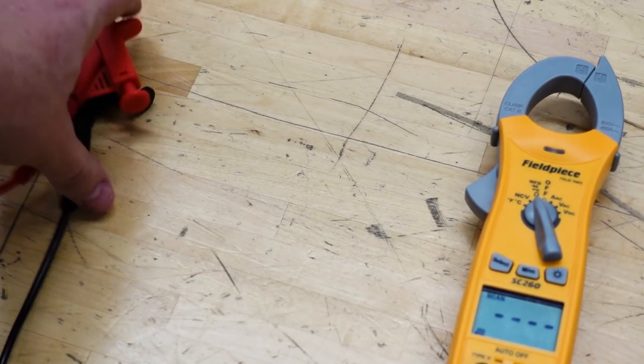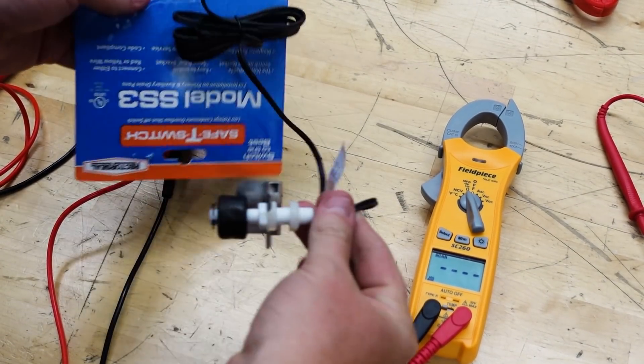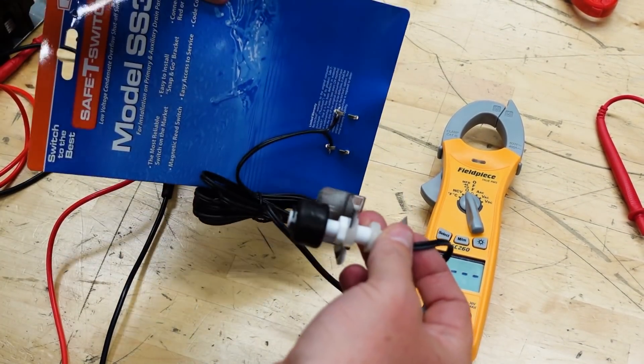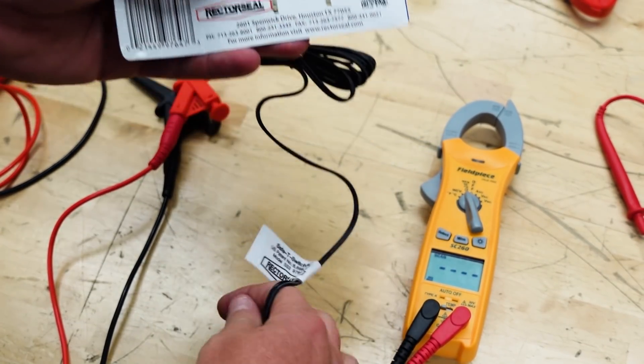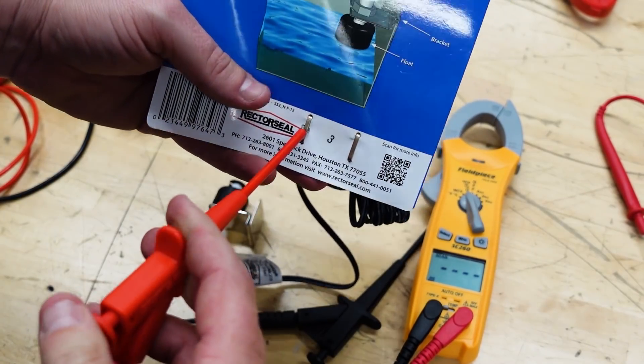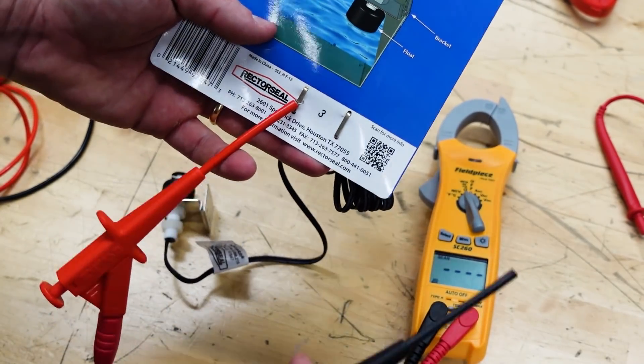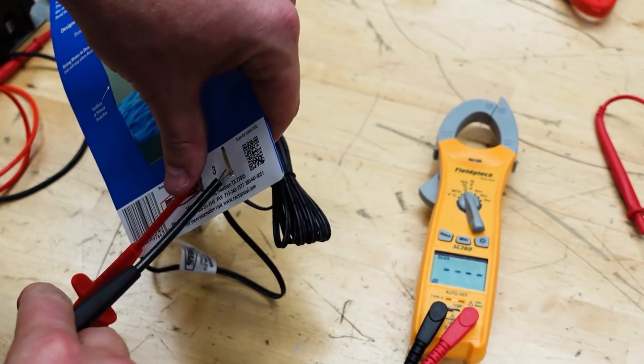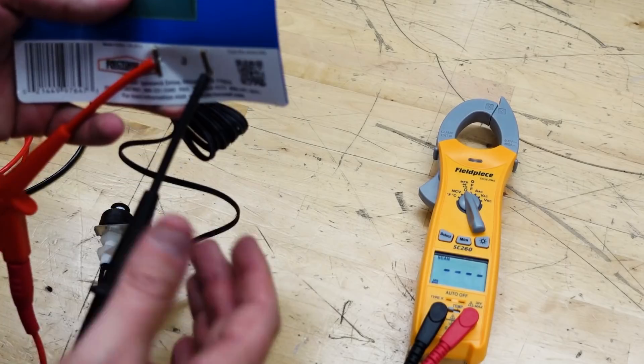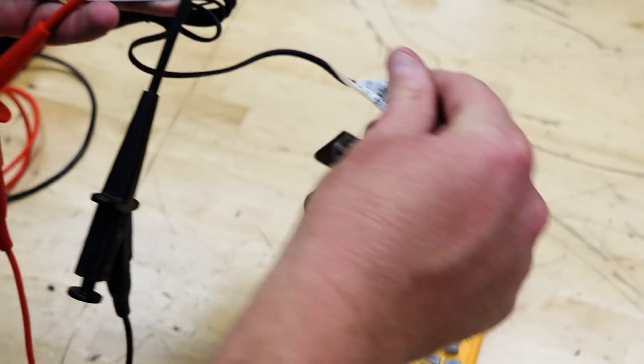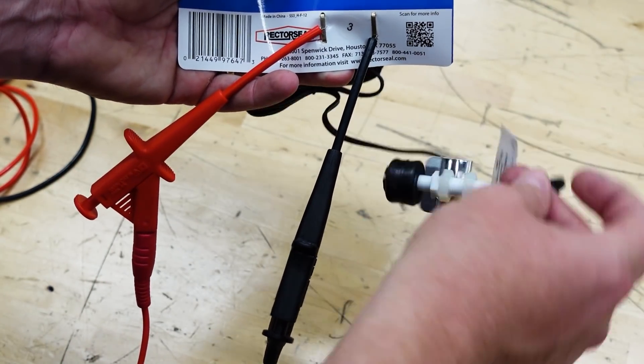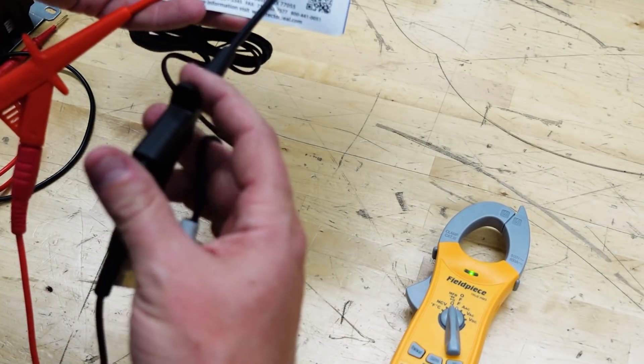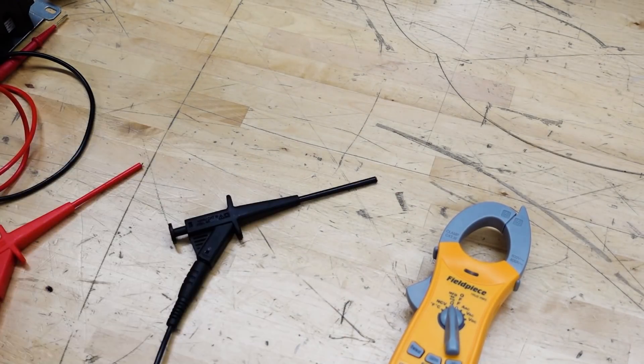So we would check to see, okay, it is open. When we energize it with the 120 volt coil, then we can make sure that the switch actually pulls in. And then we would read near zero ohms across the switch. In this case, it's three phase. So we've got three sets of independent switches. All right, let's do some more neat things. We've got a float switch here. And one kind of fun fact, I did a Facebook live video on this once, but on these Rectorseal float switches, they come with the conductors actually attached to staples on the outside. So if you want to test the thing when it's on the shelf before you even purchase it, you can actually test on these staples. You normally wouldn't do it with these weird meter leads. All right, so now we're attached there. When the switch is closed, you can hear it beeping. So there we're just using a continuity test to prove that the float switch is actually working. Pretty simple. So it goes from infinite when it's not beeping to continuity, which is a closed switch when it is.